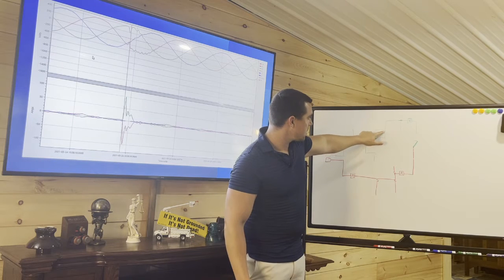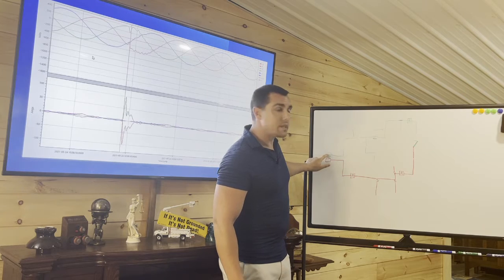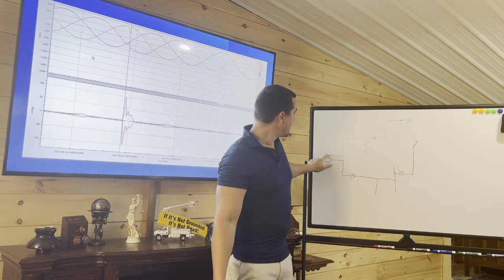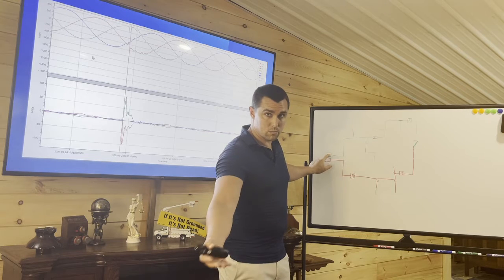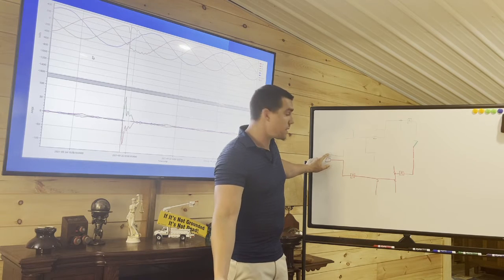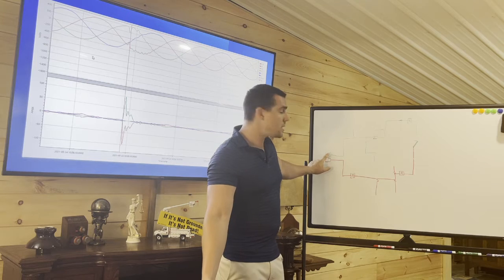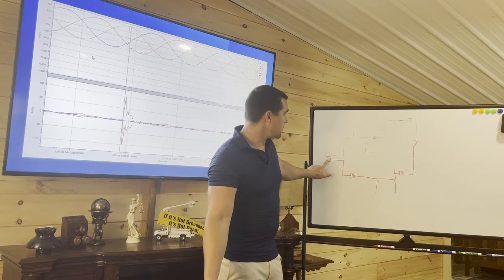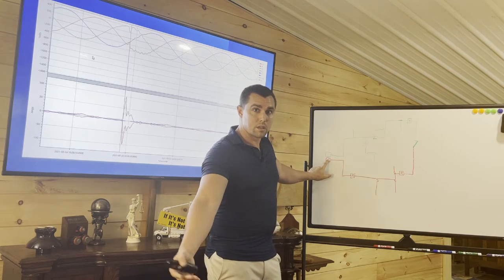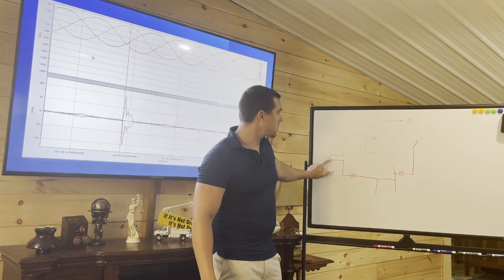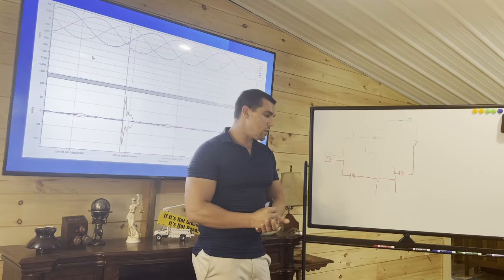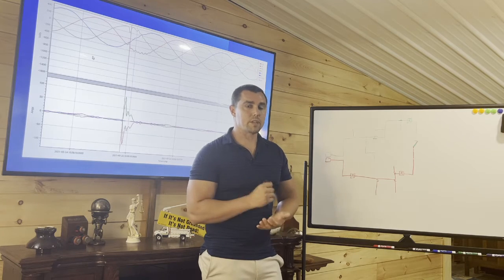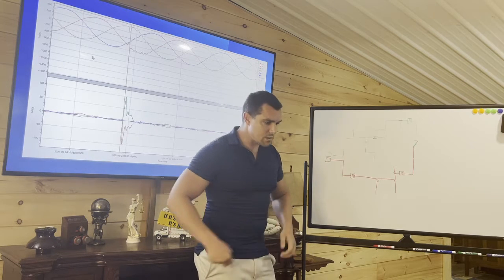So let's say this fuse is coordinated with grid feed normally. Well, your distance to your substation will be one based off of grid feed. Your distance to the fuse and available fault current will be another once it's switched around. You can run into a lot of issues, especially if you have longer feeders.